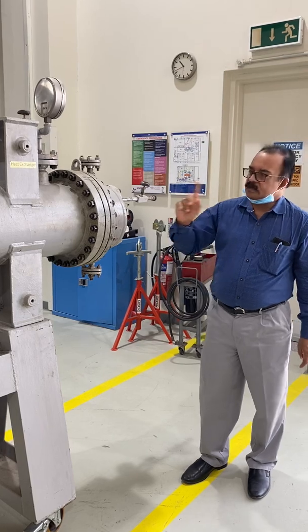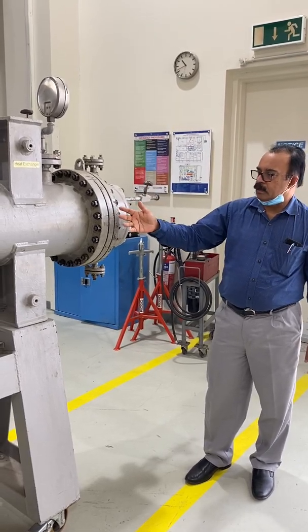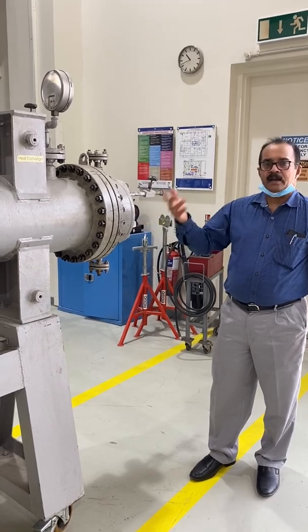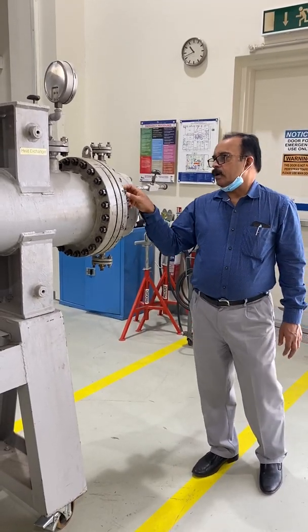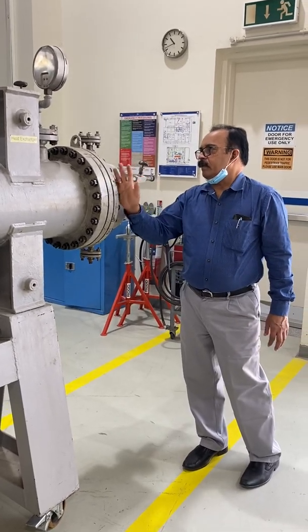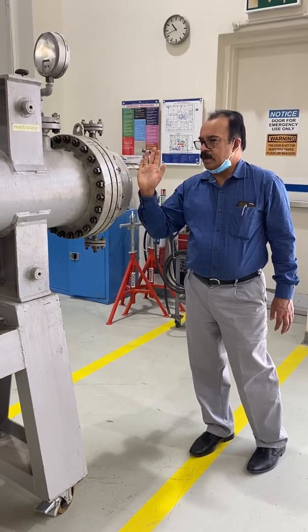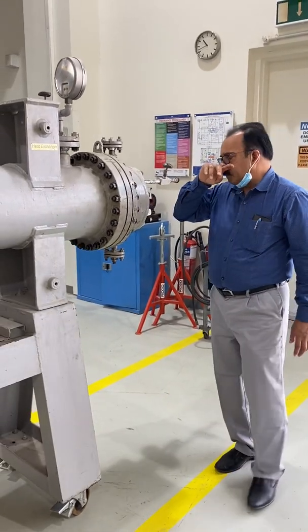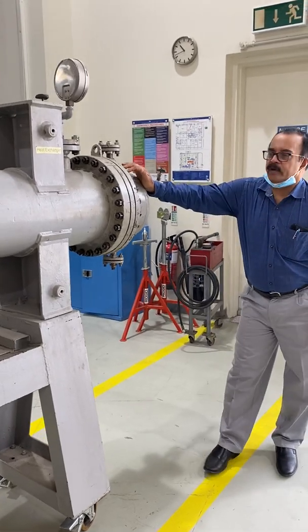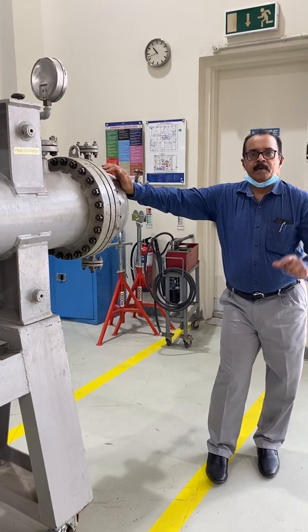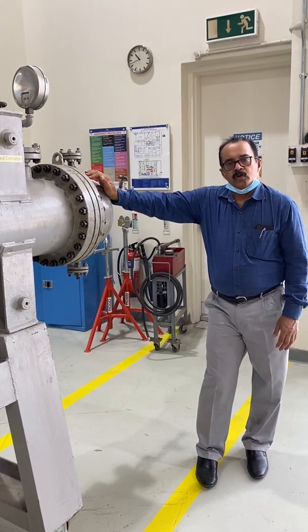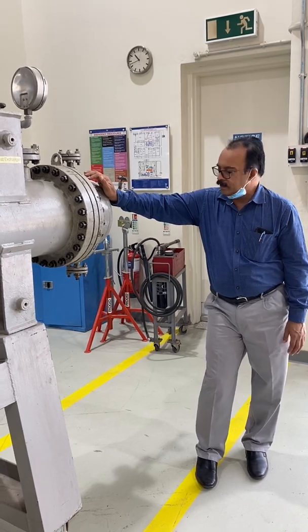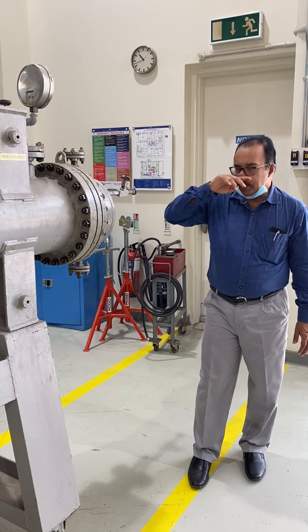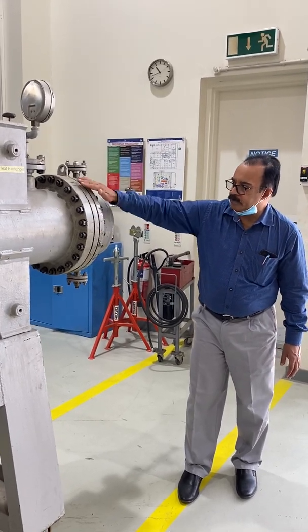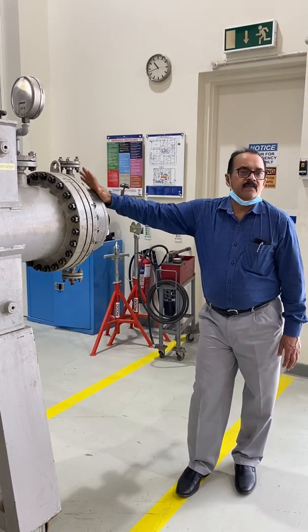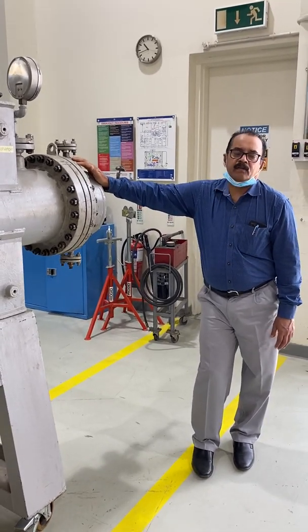And always replace the gaskets. Once it is dismantled, you cannot use them again. So take them out and fit new gaskets. Then you can put the cover, tube sheet, everything back, and after putting the new gaskets, tighten this side and that side. After that, you need to do a hydro test. The hydro test is very important, because each heat exchanger has a specification, maybe 10 bar or 20 bar. You use water to test the heat exchanger for any leak through the shell side or tube side. You can also use soap bubbles to check for leaks, and if there is no leak, then the heat exchanger is ready for operation.